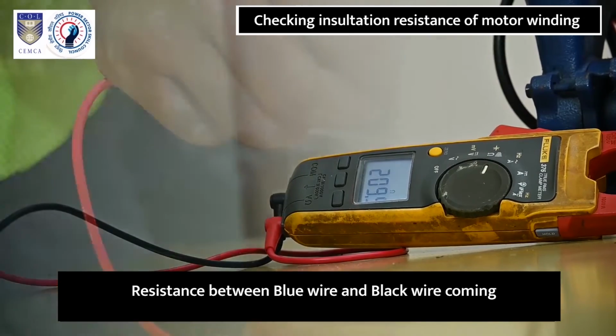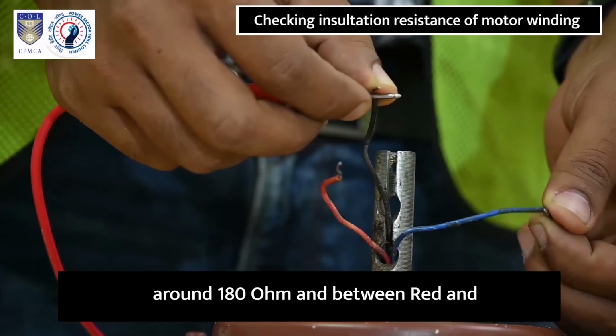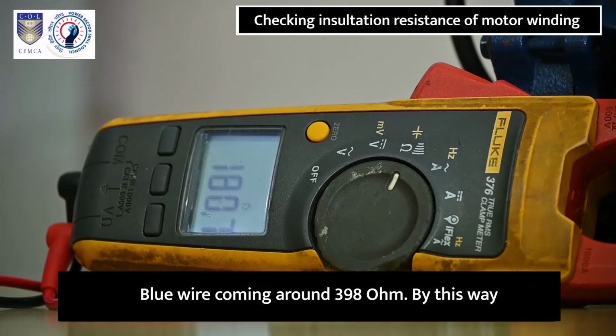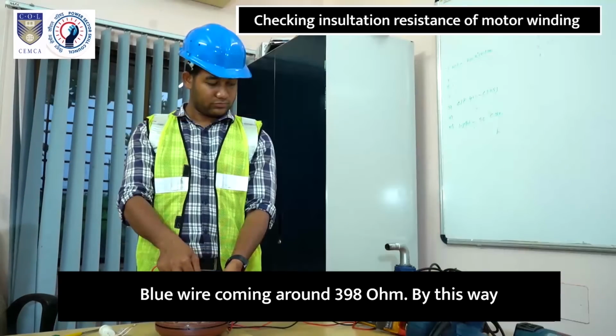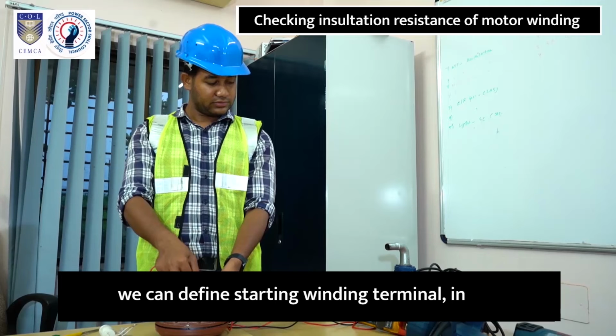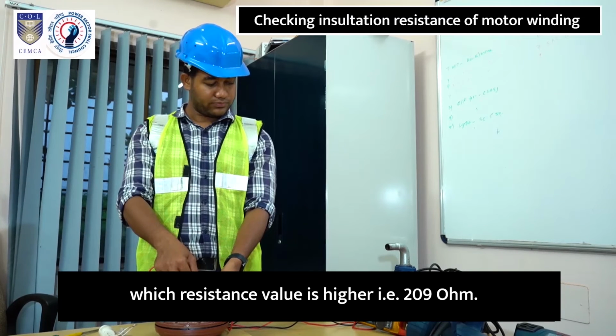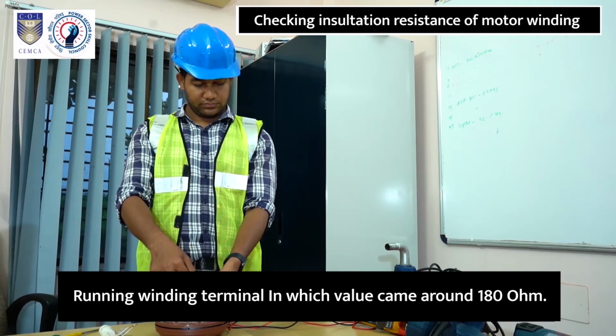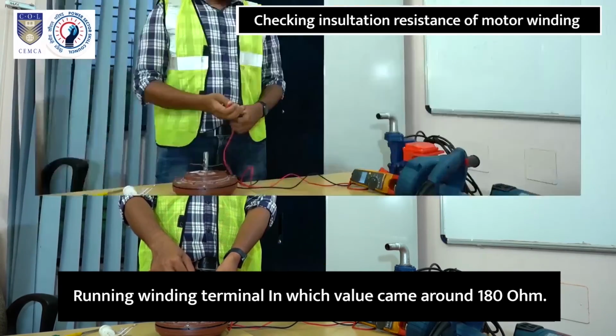Resistance between blue wire and black wire is coming around 180 ohm and between red and blue wire around 398 ohm. In this way, we can define the starting winding terminal in which the resistance value is higher, that is 398 ohm. The running winding terminal is the one in which the value came around 180 ohm.